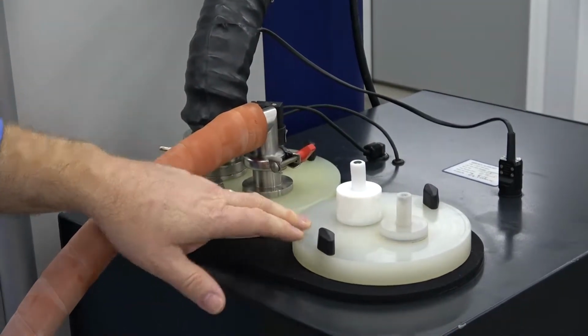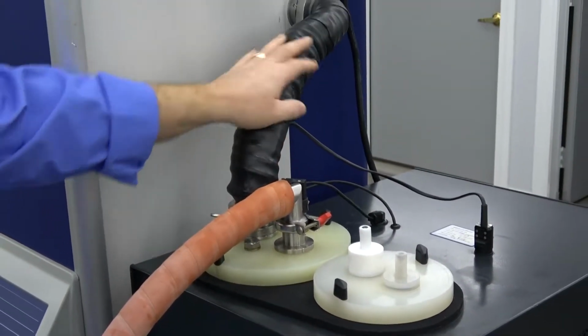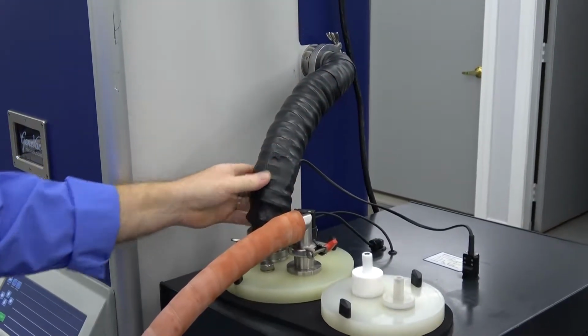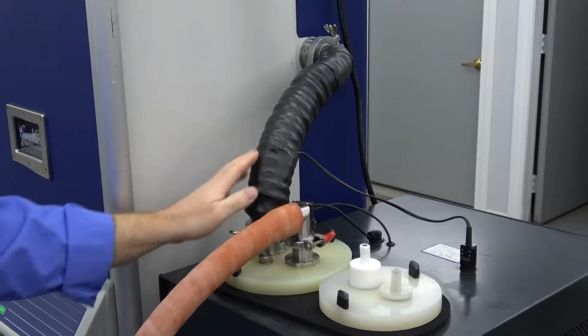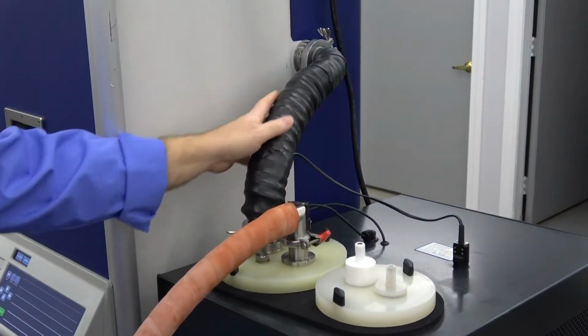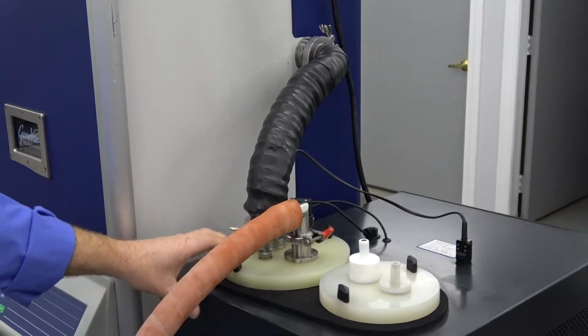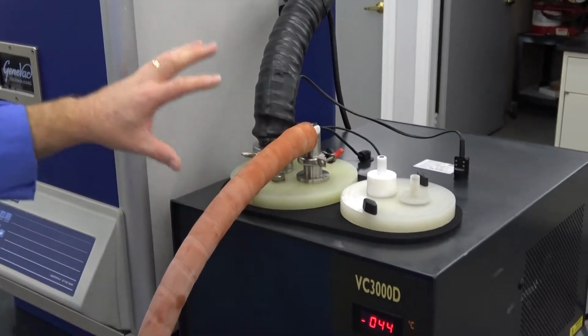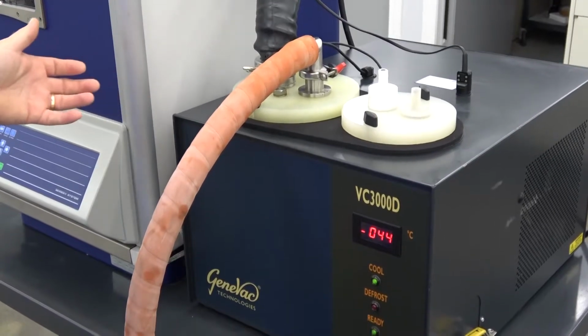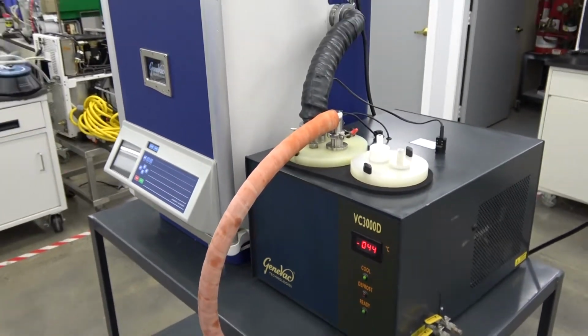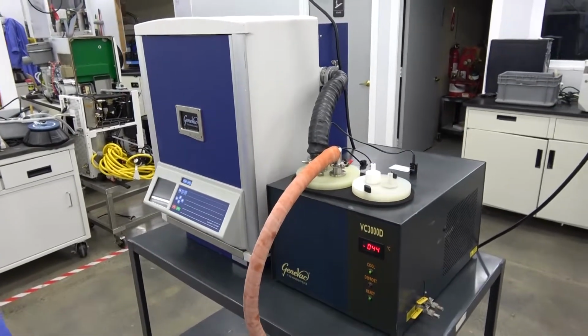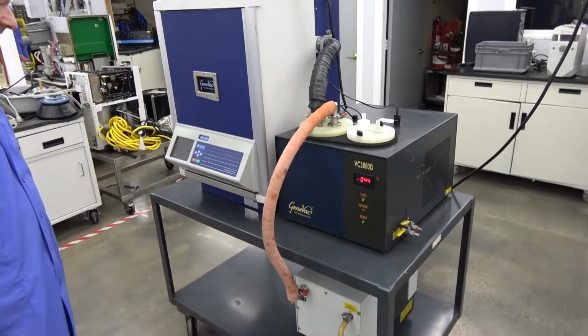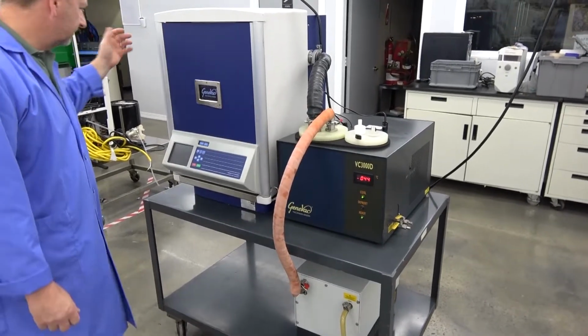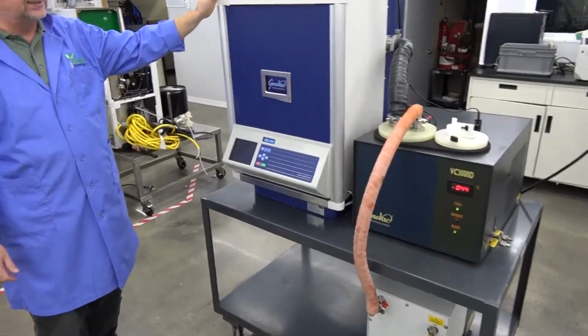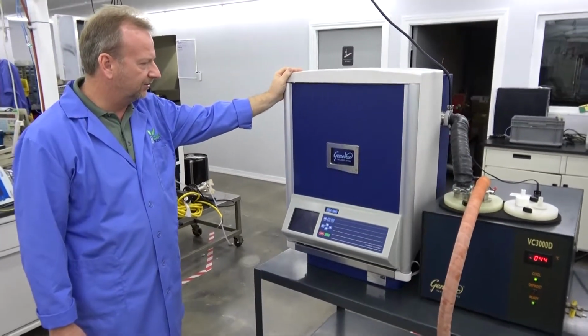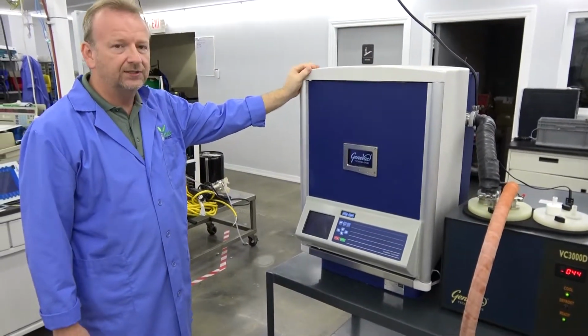So everything is complete. The heater's working great on the vacuum hose here, so you're not going to get any freezing coming up into the chamber. It's isolated off with this vacuum hose. All the freezing is just taking place down here. Everything pulls under a nice deep vacuum. I'm able to run this down to 0 millibar on the gauge, so it works great. The vacuum pump's working great. I really don't have any issues with this system, but I just wanted to point out everything on it because I did spend some time, and I just wanted to make sure that it's relayed to a potential customer.